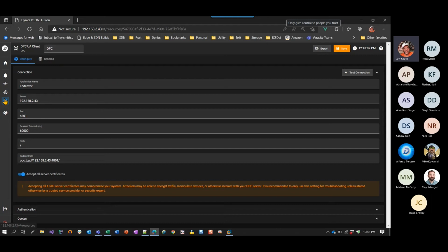You can use this to write data between different types of PLCs and different types of devices. Anything you can read, you can write out to something else. All the data types are ANSI data types, so they're very base atomic data types. For example, a DINT32 or an INT32 is the same thing as a Rockwell DINT, which is a 32-bit integer. That way we cross data types across multiple PLC types and different devices with no issue.